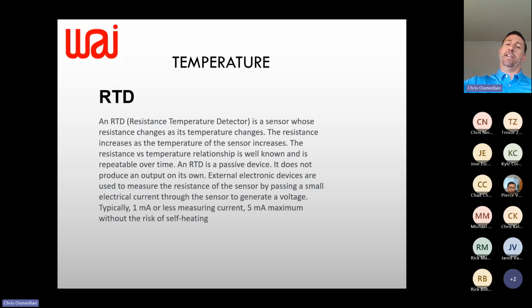And it's a pretty linear graph that says, when it's heated to this temperature, you're going to get this resistive value output from that device. And I would say RTDs are the most popular temperature sensing device as far as volume out there, in both process and industrial automation. An RTD device is very simple and very inexpensive, and you'll have that probe that's deployed. The issue with an RTD is you get a very low level resistance value that changes with temperature.